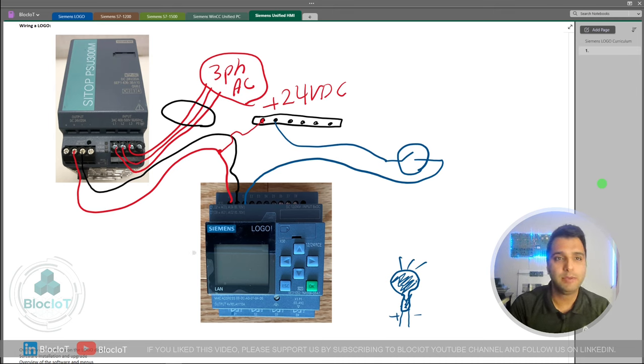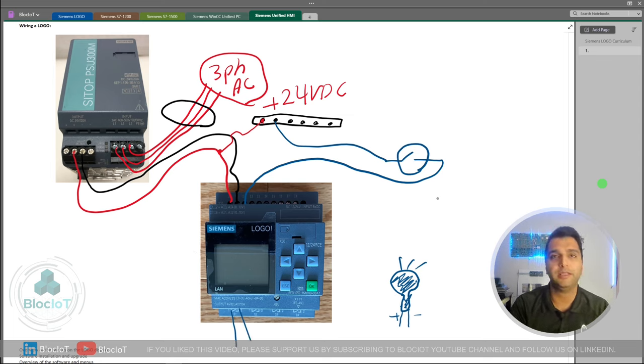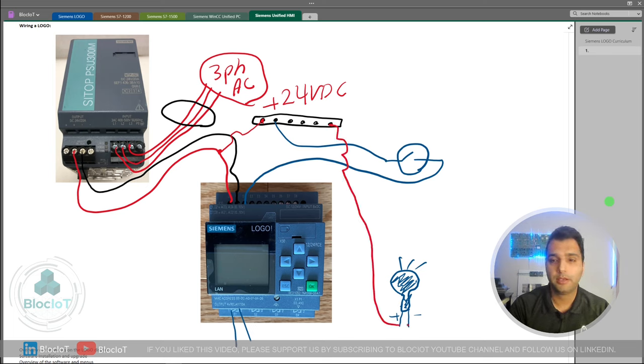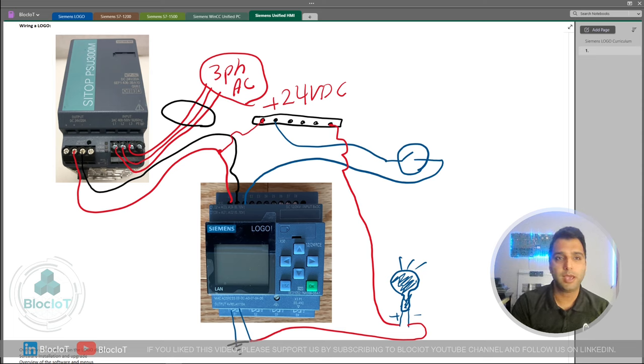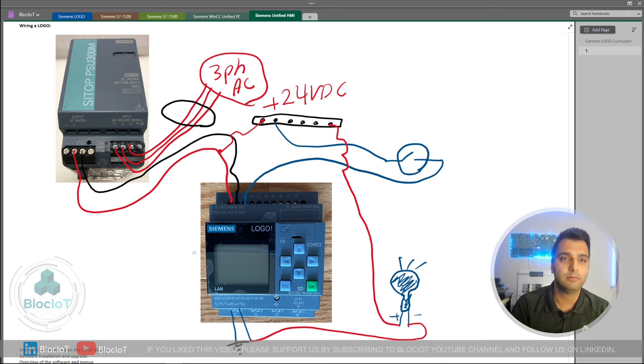In this Logo, the output is relay type, meaning the output is just a dry contact — no voltage needs to be applied. For example, with a light bulb or solenoid valve, you wire the positive terminal to the 24-volt DC, connect the minus terminal to one side of the Logo relay output, and then connect the other side of the relay to ground. This creates a closed loop: 24-volt DC from the power supply goes to the actuator, through the Logo switch, and back to ground.